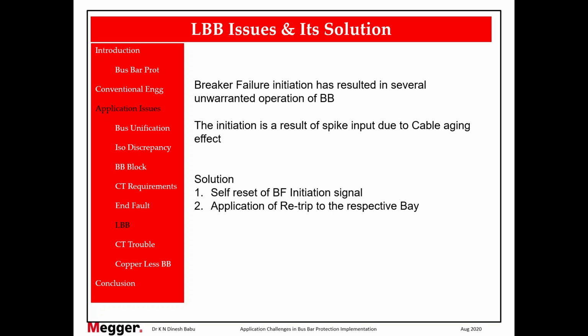Second case, you may ask that this is applicable only for 86 relay failure. What happens if the breaker itself failed? After 100 milliseconds, I will check whether that particular bay is clearing the fault or not. If it is not clearing, after another 100 milliseconds, that is total 200, anyway it will trip the bus, giving you the same solution. So this is an additional security where you can safeguard your bus bar, thereby enhancing your grid stability, because operation of the bus bar is going to shake the grid for a few milliseconds.